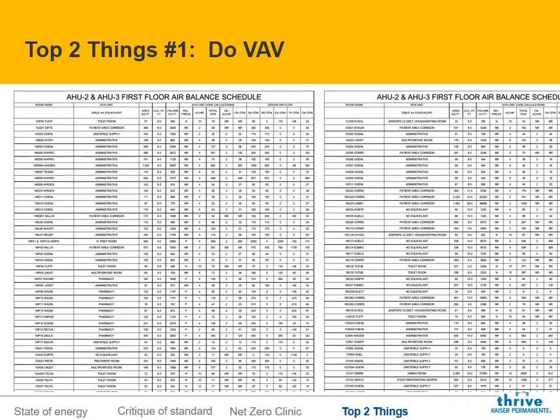And it didn't really register with me at the moment, but back at my desk a few months later, I was reviewing this job that's on the screen here. And the engineer was proposing a constant volume, 24/7 system. And I looked at the room schedule, and I don't know if you can see the room names, but I saw that about 75% of the system was administrative areas and D&T. And that's kind of when it hit me. I said, wow, we're going to spend $2 million on an air handling system and a set of controls in 2019, and we're going to put in a constant volume reheat system to serve a bunch of these admin spaces.